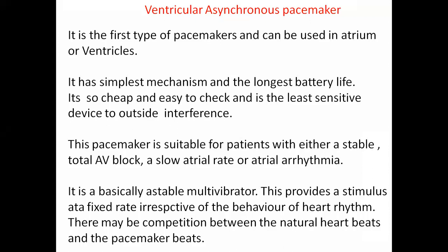So it is insensitive. This pacemaker is suitable for patients with either a stable or total AV block, atrioventricular node block, a slow atrial rate, or atrial arrhythmia. In any of these cases, we can use this particular pacemaker.